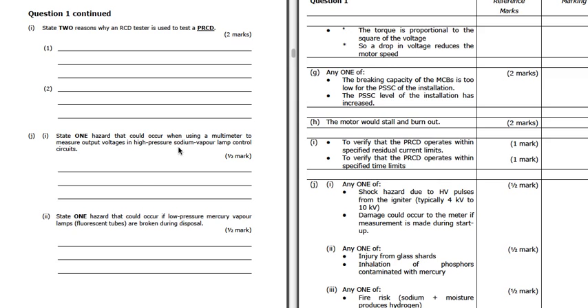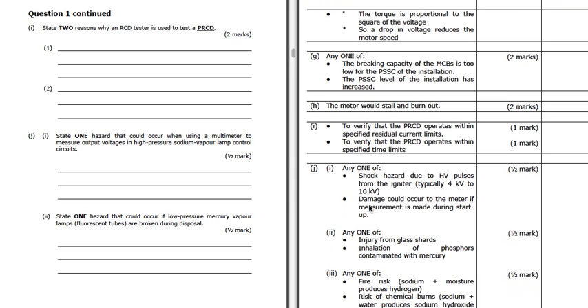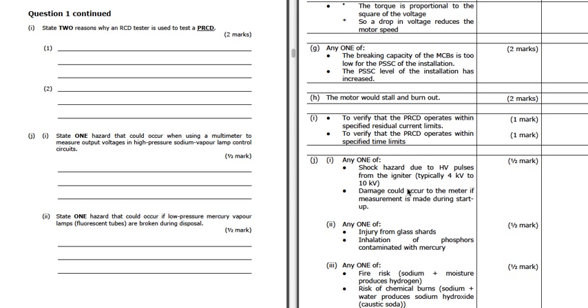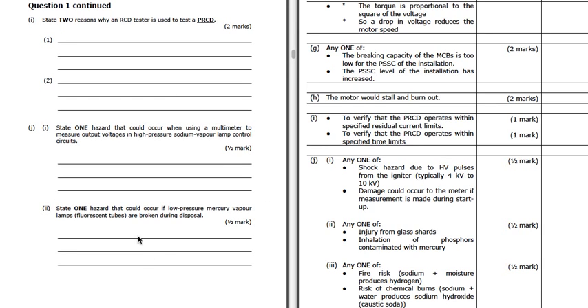State one hazard that would occur when using a multimeter to measure output voltages in high pressure sodium vapor lamp control circuits. Now these control circuits are very high voltage, so we've got a shock hazard there, typically 4 kV to 10 kV. And damage could occur to the meter if the measurement is made during startup. So it's during the startup when the lamp strikes, we've got this very high voltage, and so we could damage a meter that isn't specified for those kind of high voltages.